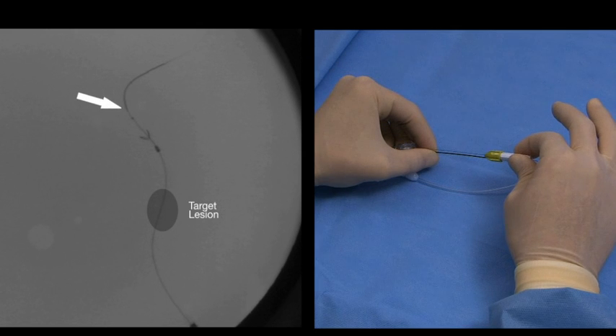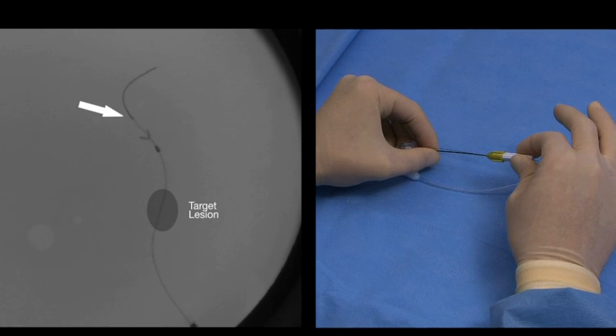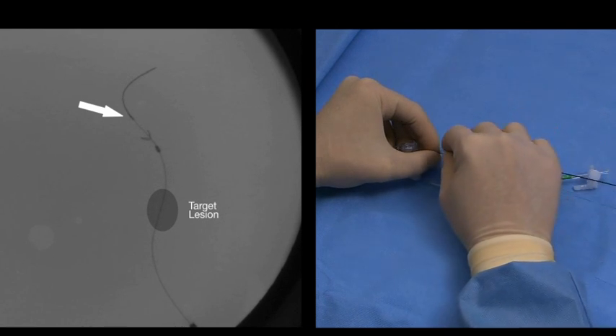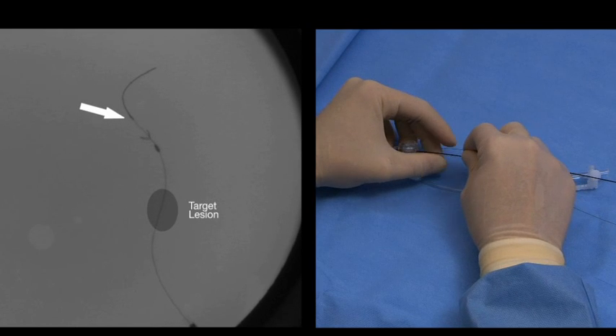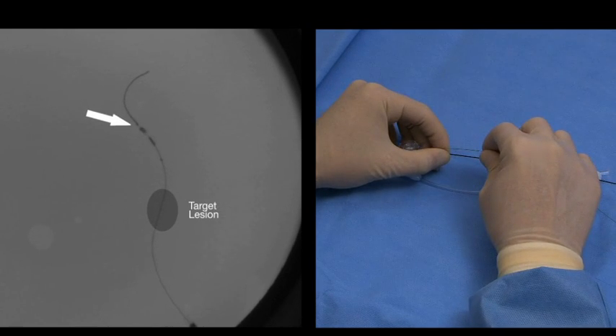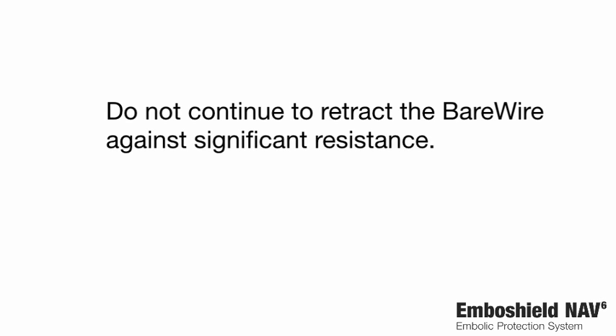Grip and retract the BareWire until the proximal radiopaque section of the wire meets the distal end of the filtration element. Continue to retract the BareWire until the filtration element is fully enclosed in the radiopaque expandable tip of the retrieval catheter. Filtration element retrieval is complete when the distal marker band on the filtration element is within 2 millimeters of the distal end of the radiopaque catheter tip. Do not continue to retract the BareWire against significant resistance.